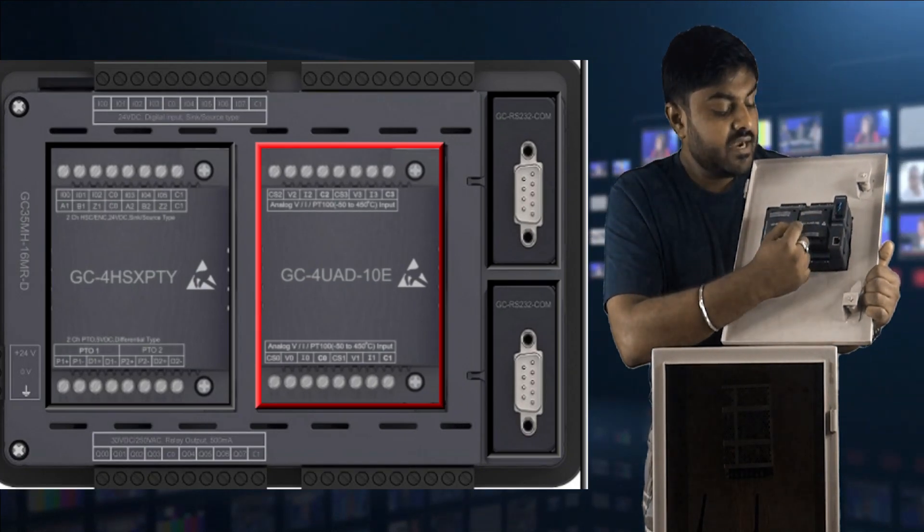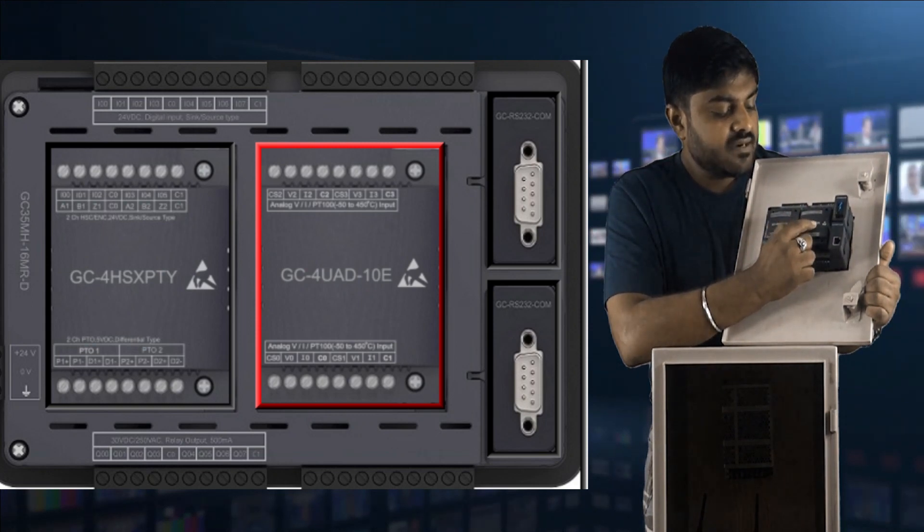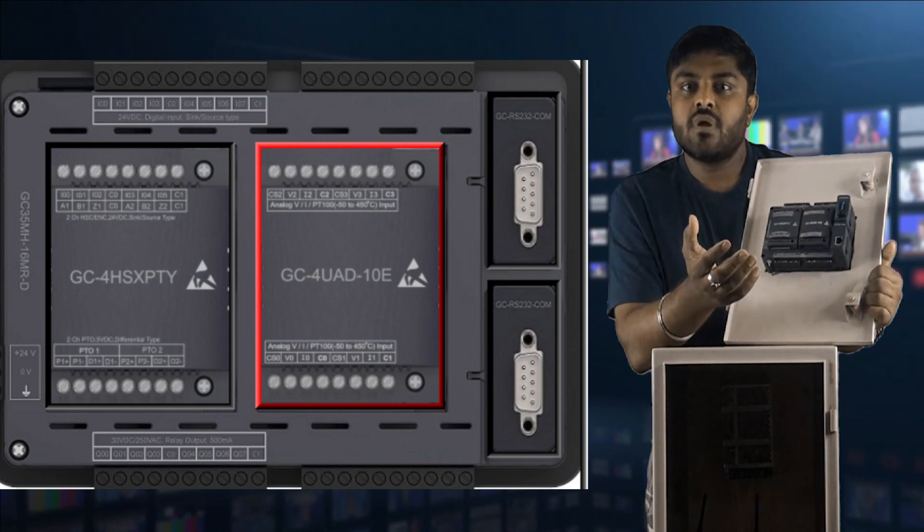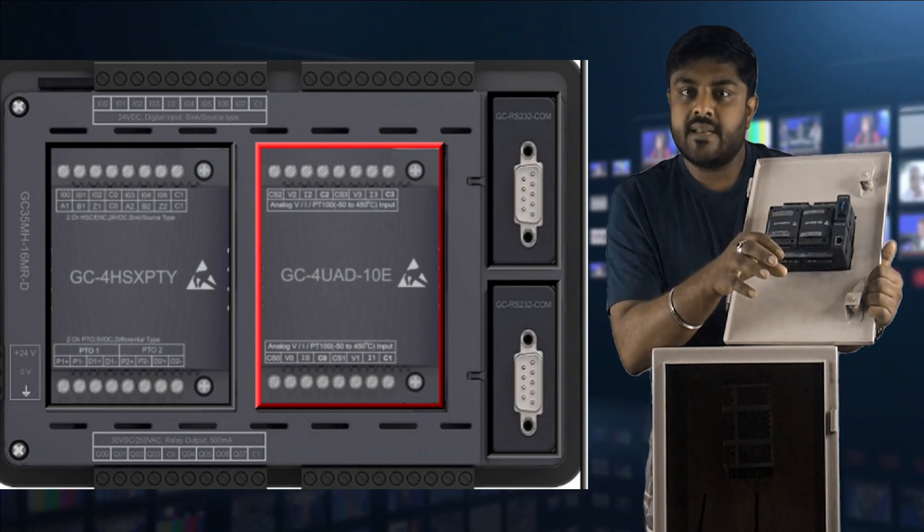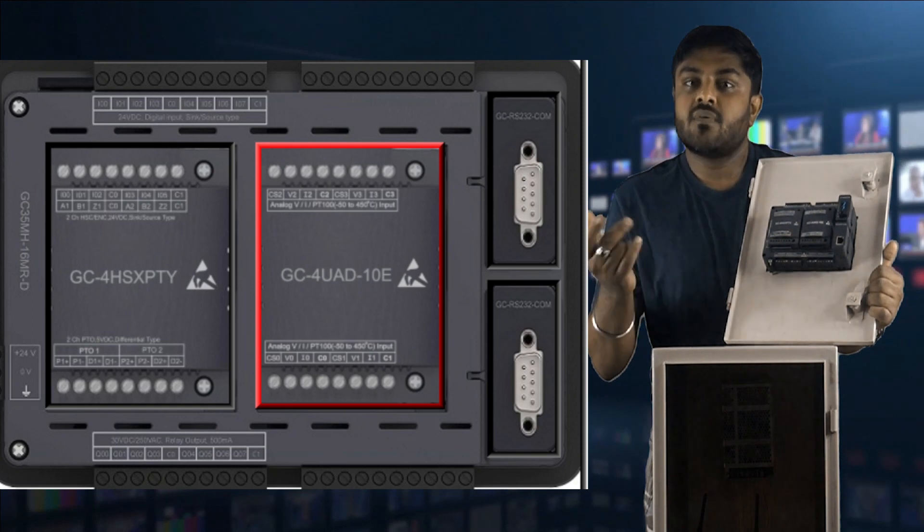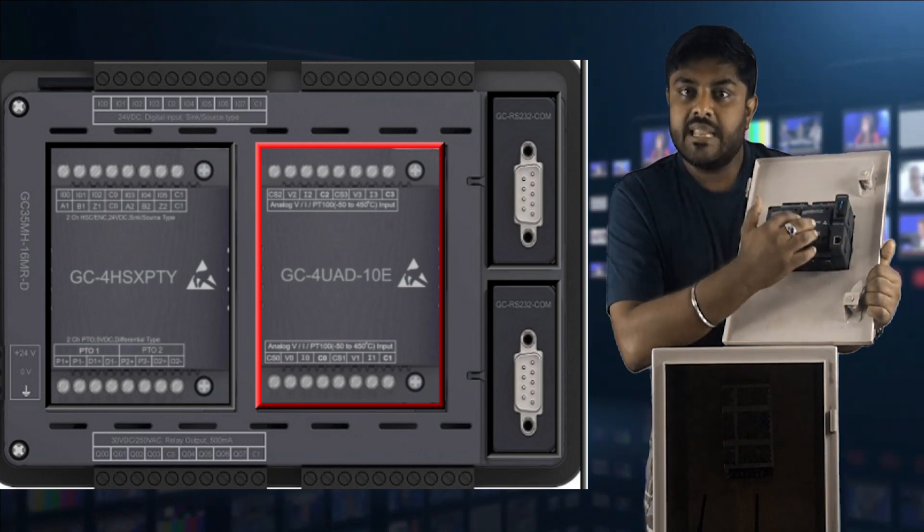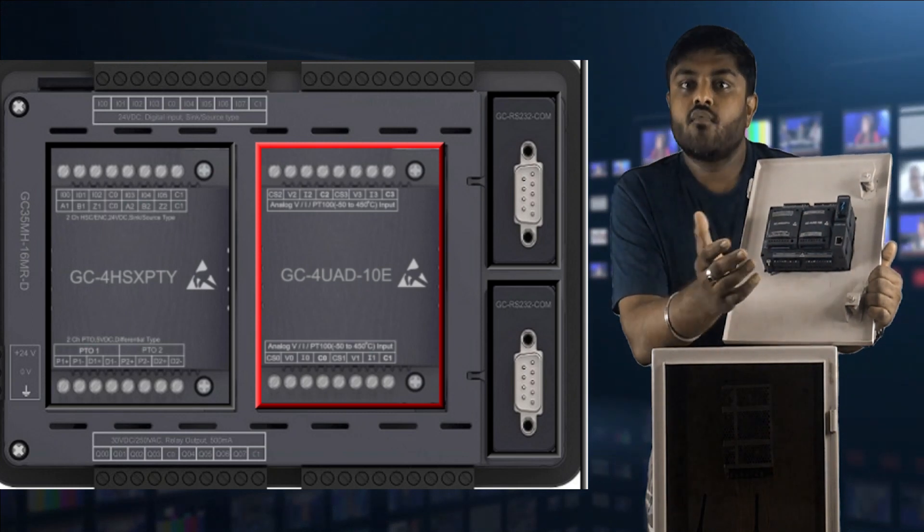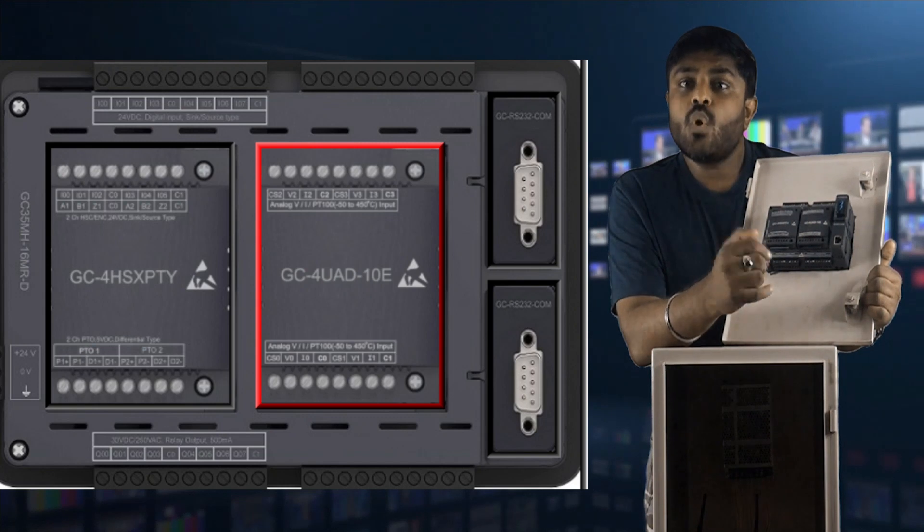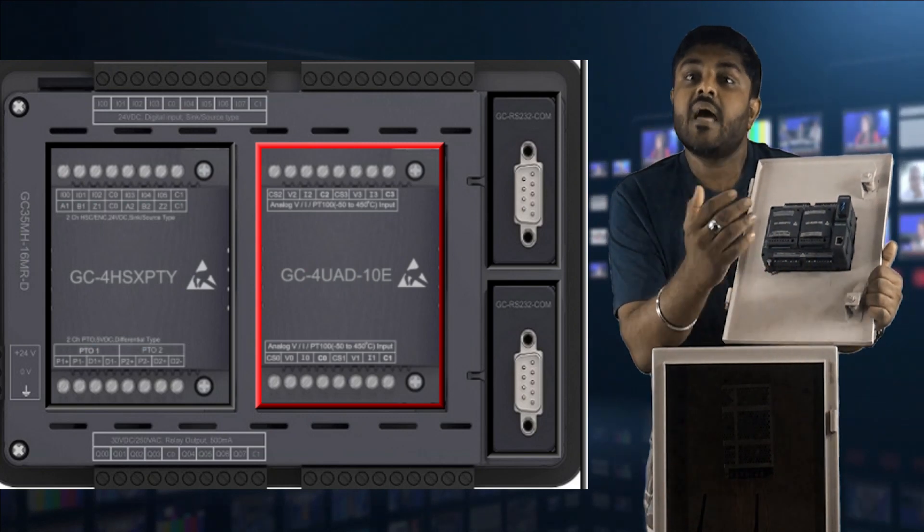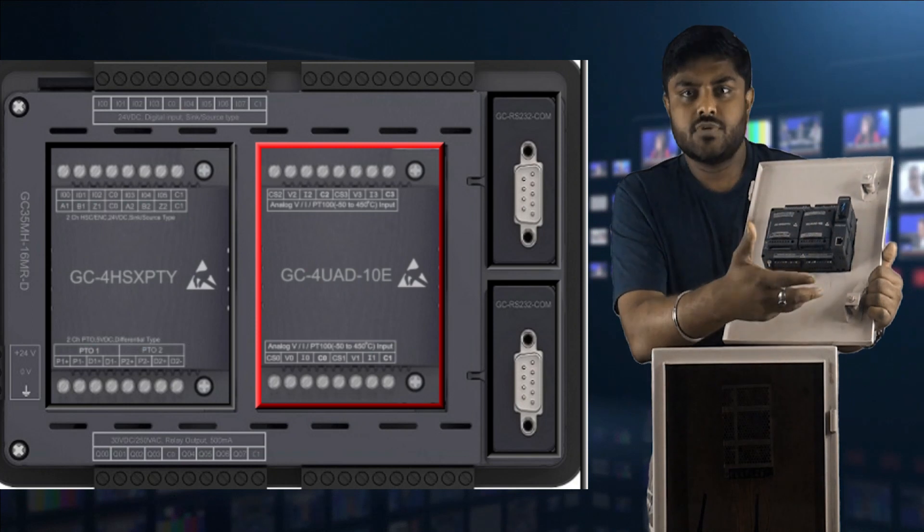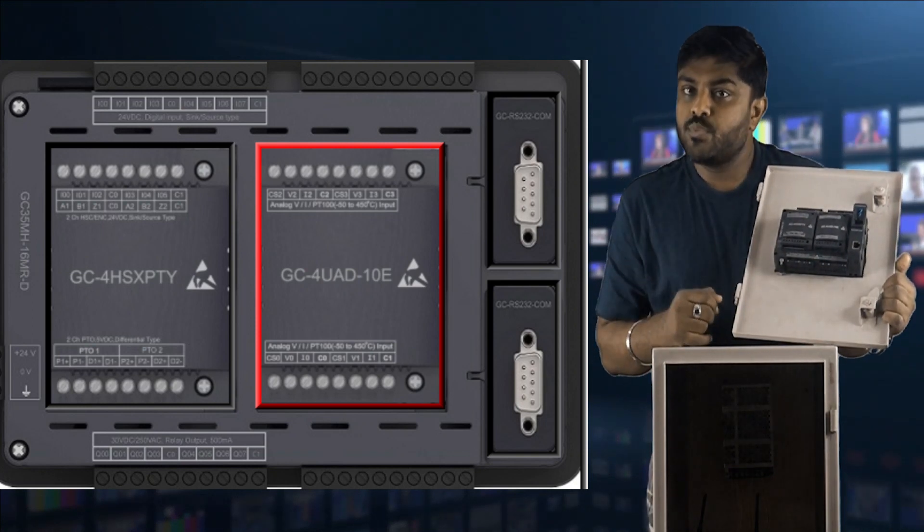In another attachment we are connected with GC4UAD-10E, which has four analog input channels. We can configure that channel as per our application. This module is universal. It can support 0 to 10 volt DC, 4 to 20 milliampere, 0 to 20 milliampere, and we can also use three-wire RTD sensor with this. It is very good PLC to kick start your automation career program.